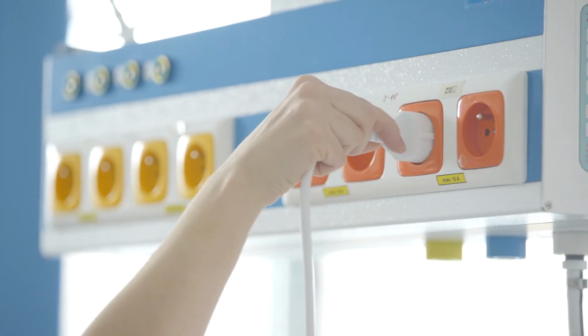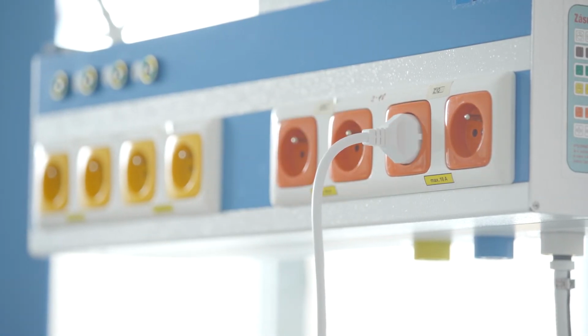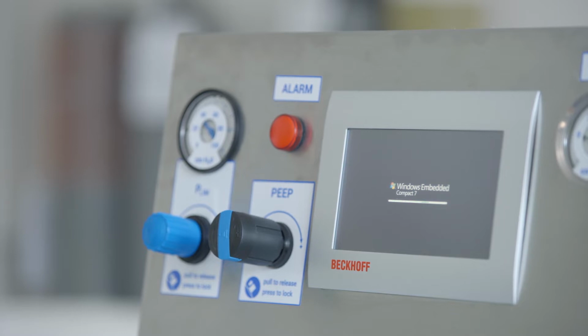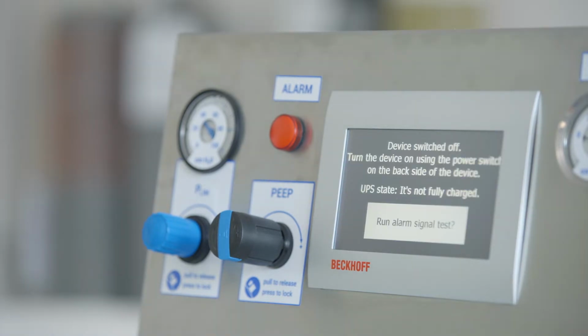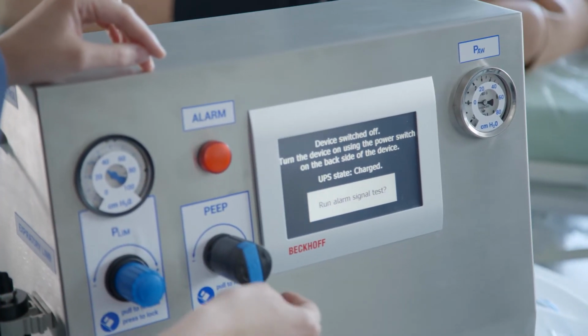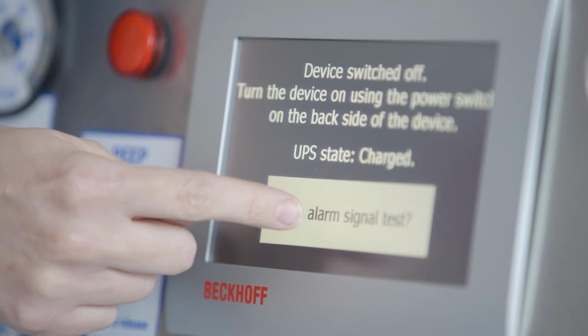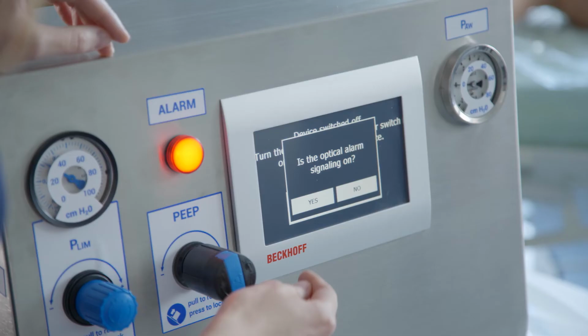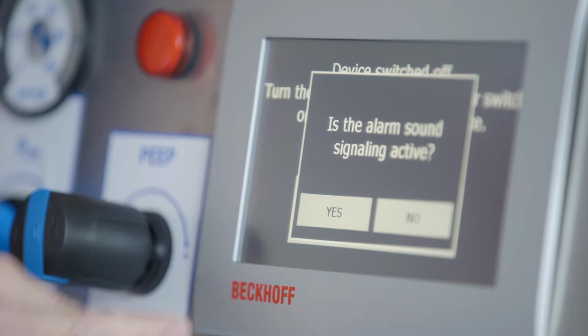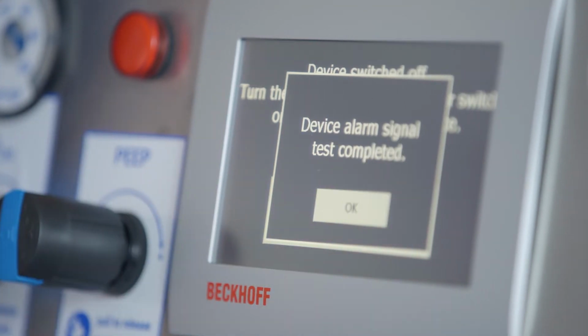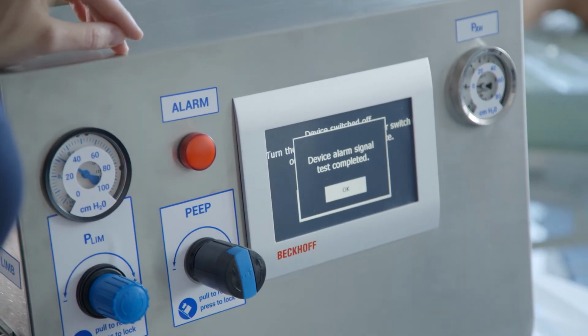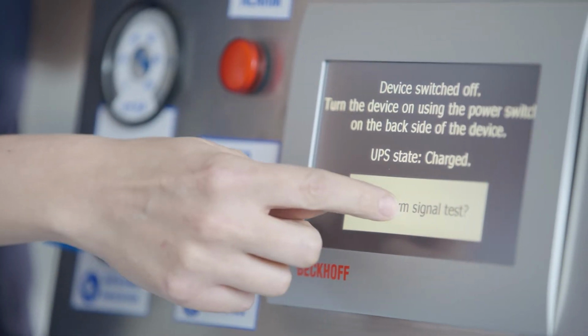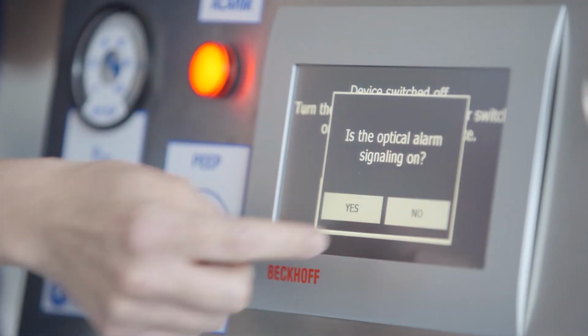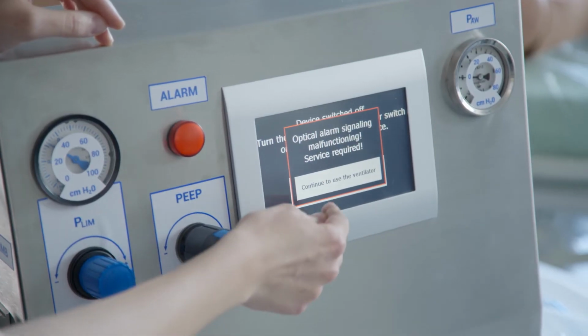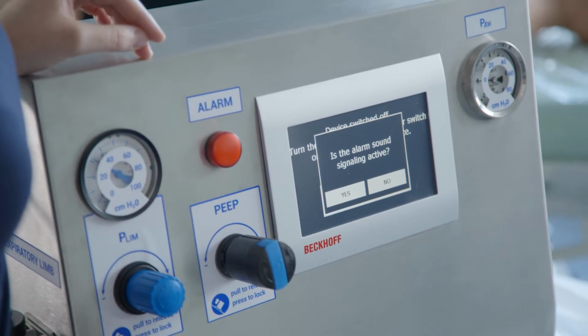In order to turn on the ventilator, plug it to the mains. Before using the ventilator, it is necessary to check the visual and sound alarm systems. We can start the test by choosing Run Alarm Test on the standby screen. If one of the alarm systems does not work, the ventilator still can be used and the failure of the alarm signaling is indicated on the screen.